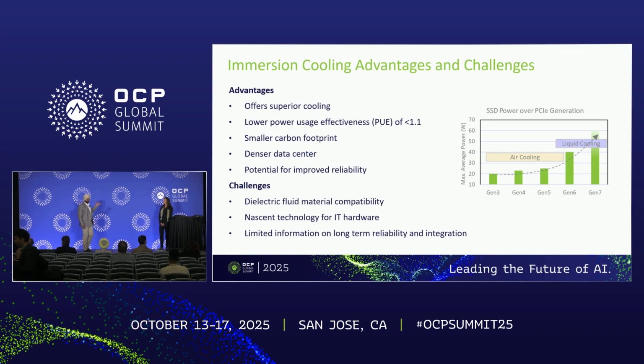I think these advantages and challenges are well known, so I'm not going to repeat them all. Immersion cooling is now a working group at OCP, and there's advantage of thermal performance, lower PUE, smaller carbon footprint, and better reliability. But the main challenge is material compatibility, and what is the validation and test criteria, so someone can say, I approve this SSD for the next 5 or 10 years, validate it, and you can put it inside the immersion cooling environment.